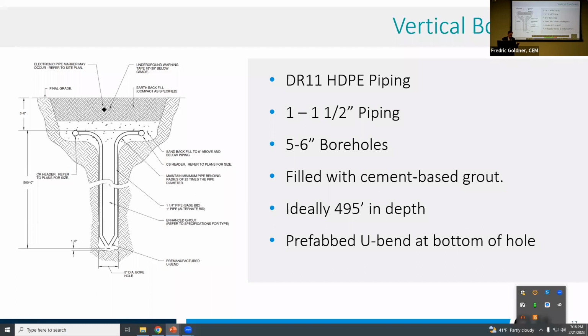But my experience is that we want to be no less than 10 feet. More than 10 feet is always greater, but I'm more concerned about the thermal penalty. Like, what can the energy in this loop do to the foundation and or vice versa? I've read of some installations where the loop field was so close to the foundation that they were actually conditioning the foundation. They were losing energy to the foundation. So without speaking out of my league, I would say that our typical borehole spacing is 20 feet borehole to borehole, which means that we've got 10 foot of radius. Okay. If I settle on 15 feet and I get buy-in from my structural guy, that I'm not going to have any effect on what he's doing with his footings or his pylons, then I'm good to go.